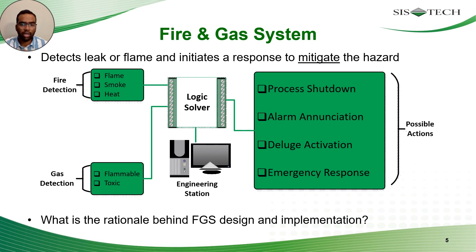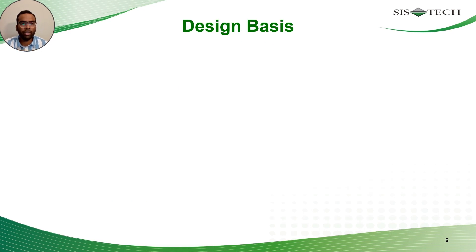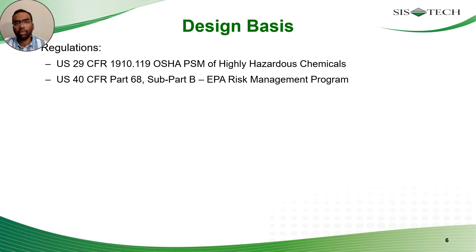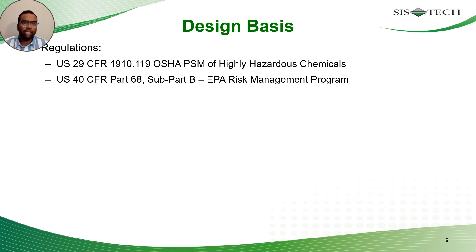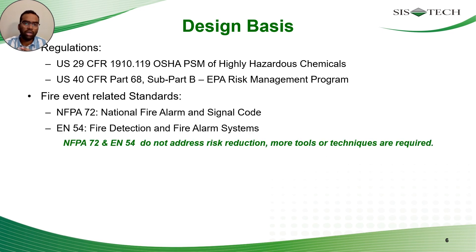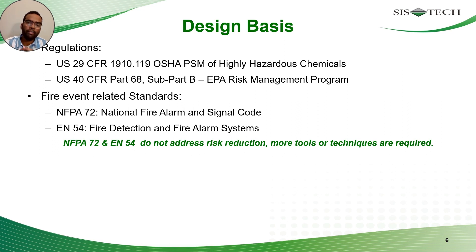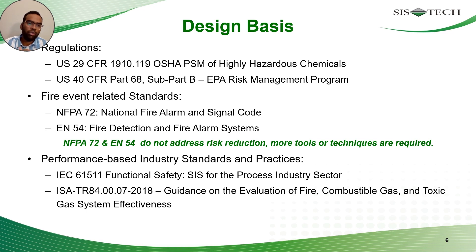What is the rationale behind FGS design and implementation? In the USA, two regulations are applicable to chemical processes: OSHA PSM and EPA RMP. When it comes to detection of events resulting in fire, the industry follows NFPA 72 and European Norm 54. However, these do not apply to toxics at all. While they provide strong prescriptive guidelines as a basis for FGS design, they are not enough since they lack a performance-based approach and do not address toxic releases. Hence, more tools and techniques are required.